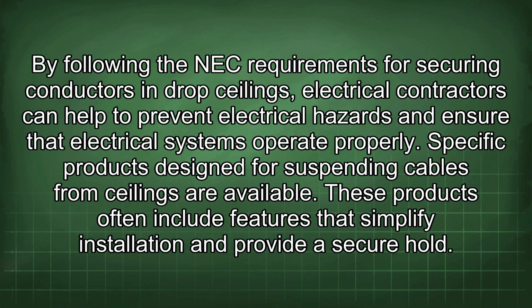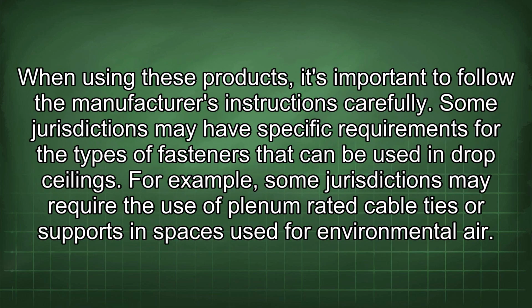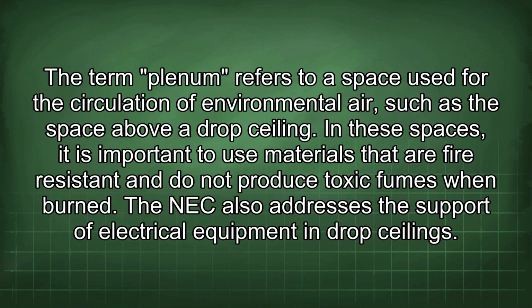Specific products designed for suspending cables from ceilings are available. These products often include features that simplify installation and provide a secure hold. When using these products, it's important to follow the manufacturer's instructions carefully. Some jurisdictions may have specific requirements for the types of fasteners that can be used in drop ceilings. For example, some jurisdictions may require the use of plenum-rated cable ties or supports in spaces used for environmental air. The term plenum refers to a space used for the circulation of environmental air, such as the space above a drop ceiling. In these spaces, it is important to use materials that are fire-resistant and do not produce toxic fumes when burned.